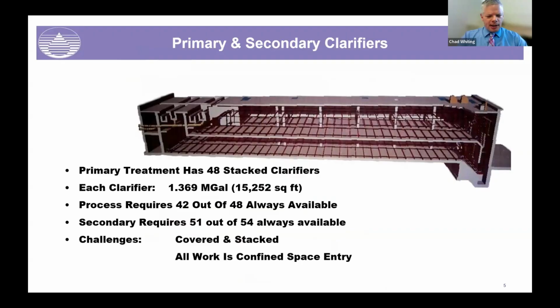This is a clarifier schematic. We had a number of space-saving technologies to be able to fit this much treatment in such a small footprint. So one of the space-saving technologies is stacked clarifiers. This is a design taken from Japan. So we have 48 primary clarifiers that are stacked, 1.3 million gallons apiece. And we use 22 of those in dry weather flows, but we need 42 tanks to meet our maximum flows of 1.3 billion gallons per day. So we have quite a bit of redundancy.